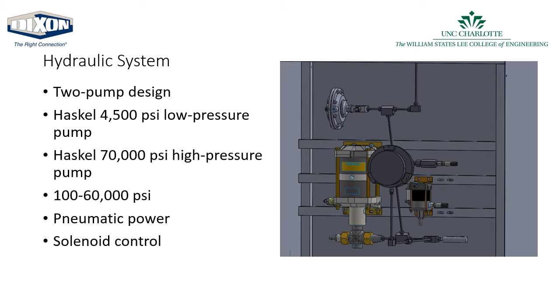For our hydraulic system, we've gone with a 2-pump design, pairing a 4,500 psi low pressure pump with a 70,000 psi high pressure pump. This lets us accurately produce pressures from 100 to 60,000 psi for static pressure tests, and gives us a small amount of insurance at the top end in case of problems with the pressurized air supply, as this is a pneumatically powered system controlled by a set of solenoids.